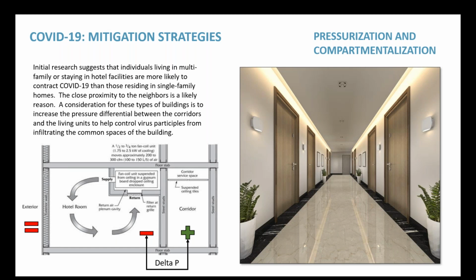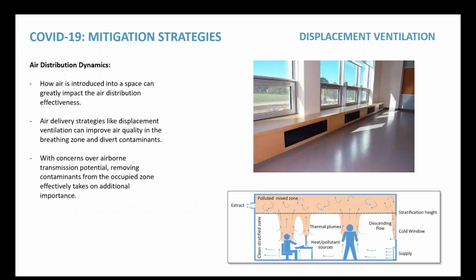So it's very important to look at these different building pressurization techniques, whether it's pressurizing a corridor so that the air that's inside of a unit stays in that unit and does not find its way out, or if you're looking at gym spaces in a residential building, or in general lobbies, things of that nature. It's very important to analyze these different pressure regimes to make sure that you have a system that is going to keep people as safe as is reasonable.